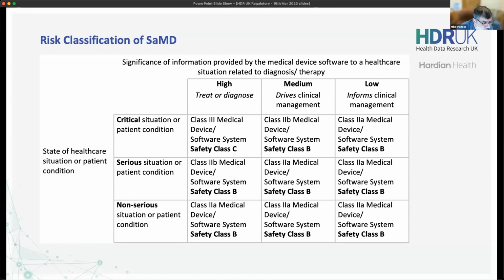So where did I get to? How do you set up usability studies for software as a medical device? Perhaps we'll get back to that one a bit later when we talk about risk. Spoiler for that, there are two types of usability we normally talk about, formative and summative. Are you informing your design? So asking people's opinion about, is the font big enough? Can you understand that language that we're using? Are the little cartoons and things actually making sense? Does the flow through the software make sense to you? That's formative. Do loads of that as much as you can.